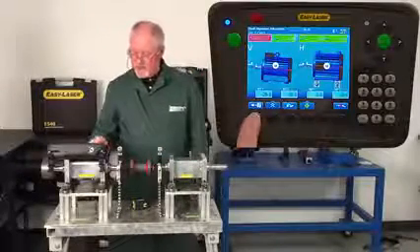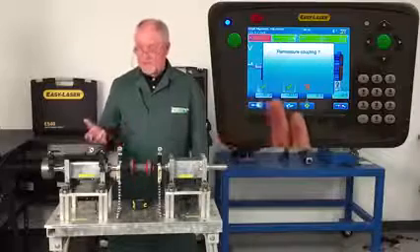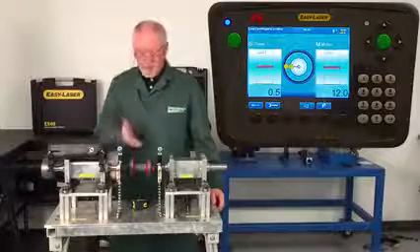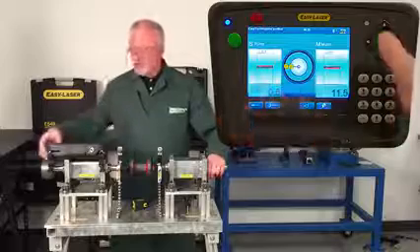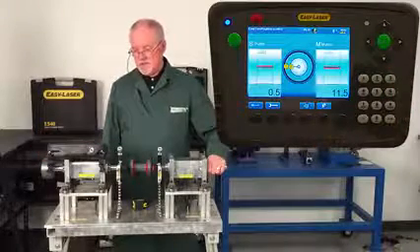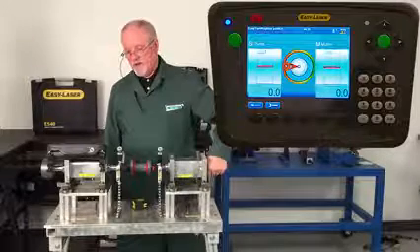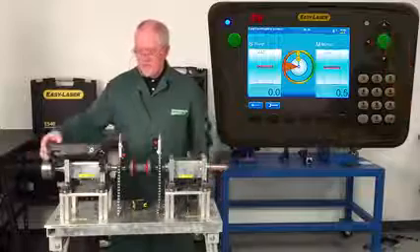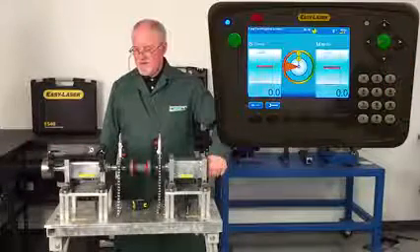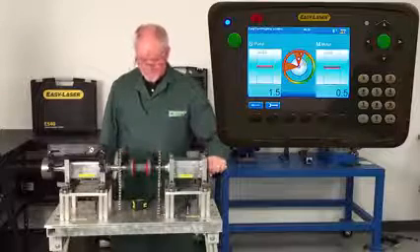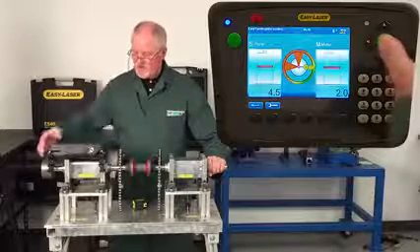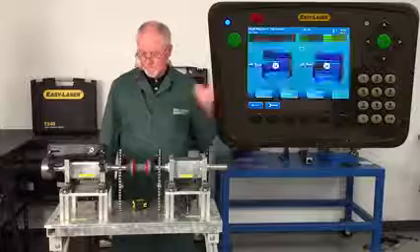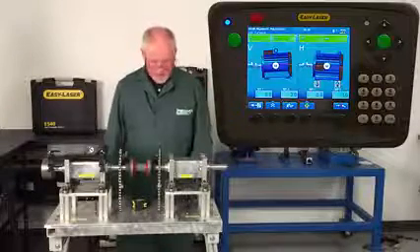And you can see the horizontals come into alignment, but we do need to remeasure. So this button here, I press the button and it prompts me. It says remeasure the coupling. I say yes. I'm going to start right there. I can start anywhere in the rotation, so this is good at any place. That's one reading. I'm going up to the top. There's two readings. I'm taking my time. Three readings.